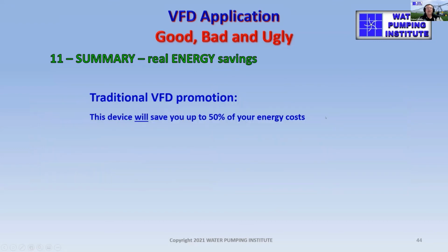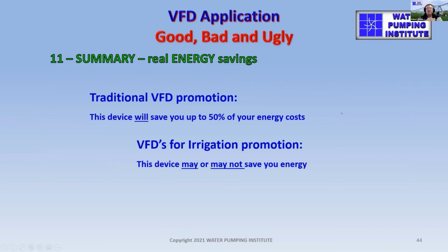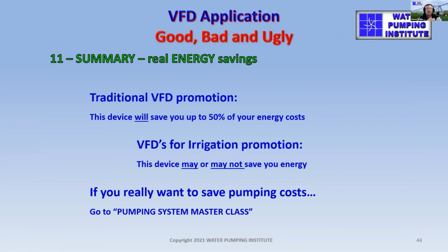So your traditional VFD promotion says this device will save you up to 50% of your energy costs. That implies that you're pretty much always going to save energy. What we should be saying is this device may or may not save you energy. That's the reality of using VFDs for irrigation. If you really want to save energy, we should be looking further than VFDs. We should be looking at what's inside the Pumping System Masterclass, and that's the other major course that we run, and it is aimed specifically at saving large amounts of energy on irrigation systems.